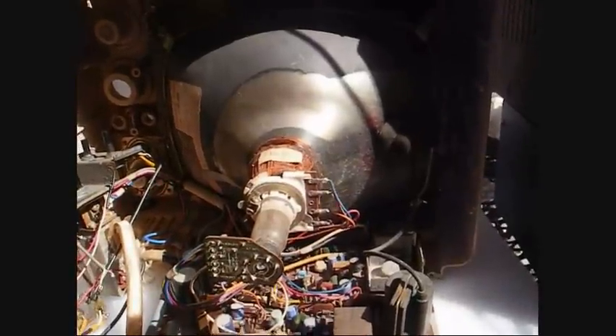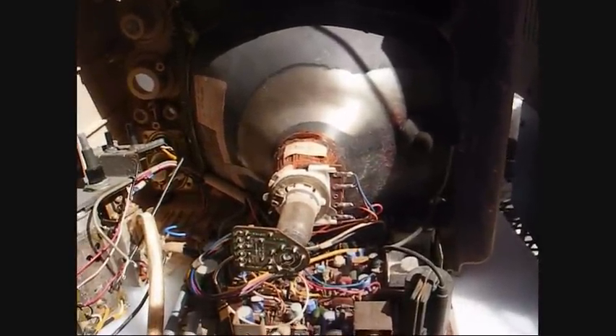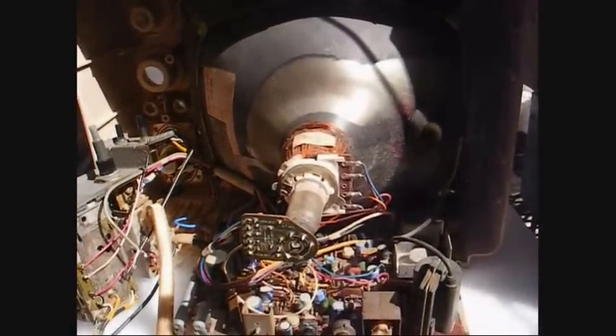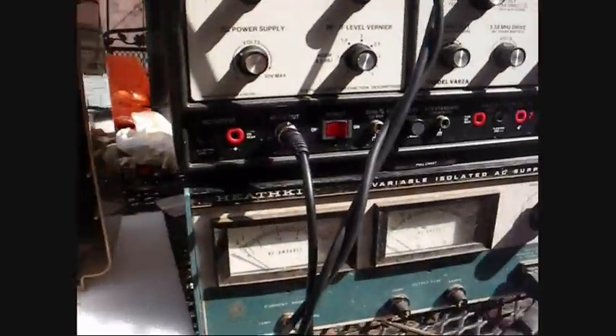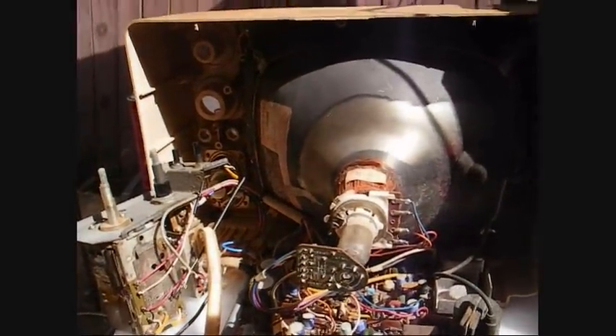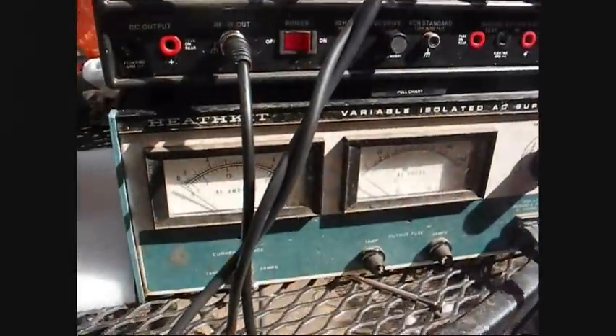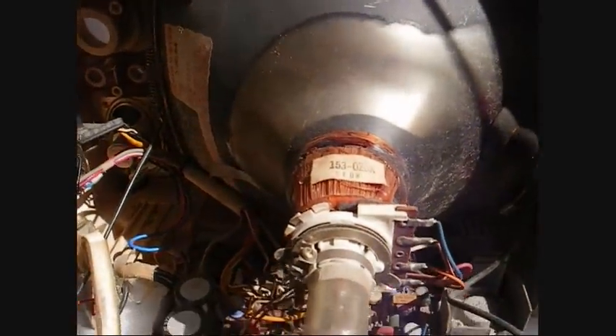When troubleshooting any power transformerless hot chassis equipment with AC operated test equipment, you should always plug the equipment under test into an isolation transformer to prevent possibly damaging the equipment and/or the test equipment. Just better to be safe than sorry.